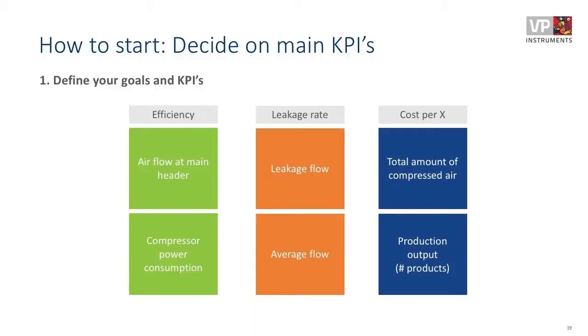So how to start with monitoring? I will lead you through a step-by-step plan. So this is the first step. Define your goals and define your key performance indicators. This is an example of typical key performance indicators you could use. One is efficiency, so the airflow at the main header divided by the total power consumption of all compressors. That gives you a good baseline of how good or how bad your system is in the beginning, and if you do a good job, then you will see that the efficiency will get better over time.